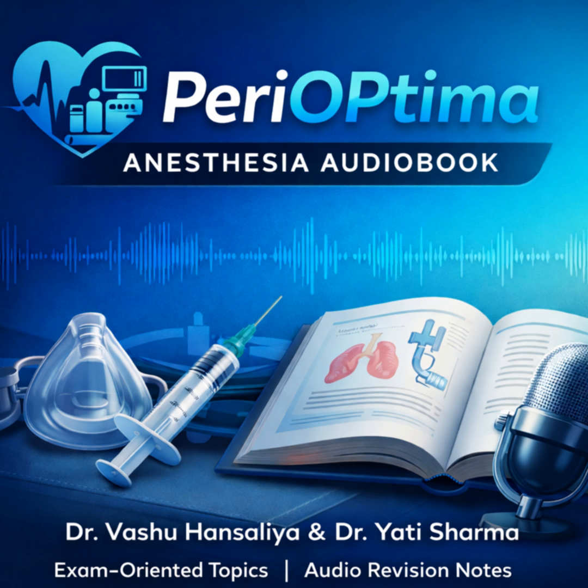Okay. And finally, the hour limits. Right, this is the hard ceiling. The pump can be programmed to limit the total volume delivered in, say, 1 hour or 4 hours. Morgan mentions a 1-hour limit of roughly 15-25 milliliters for epidural PCA, for example. It's just a final fail-safe against machine error or, I suppose, extreme patient error.